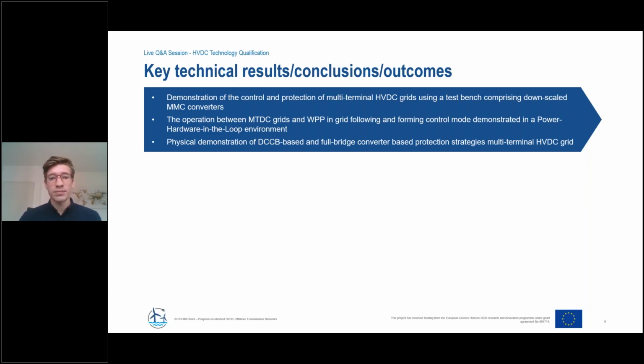Moreover, we showed that it is possible to operate HVDC grids in combination with wind power plants, which can be either in grid forming or grid following mode, which we demonstrated via power hardware in the loop testing. Last but not least, we carried out first physical demonstrations of a DC circuit breaker concept and the protection based on full bridge converters within a multi-terminal test bench. It was a downscale multi-terminal DC grid test bench, but these were the first demonstrations of these concepts.